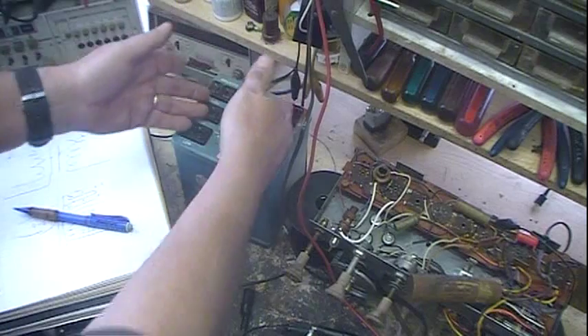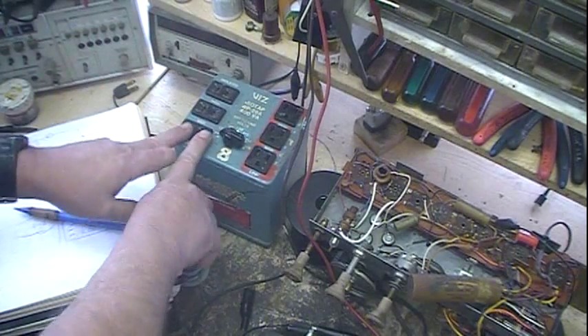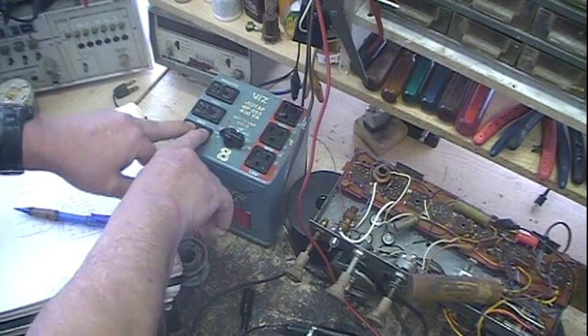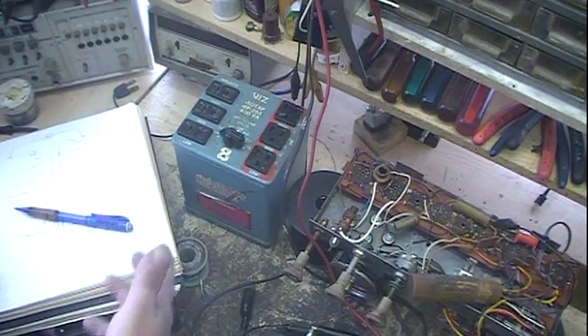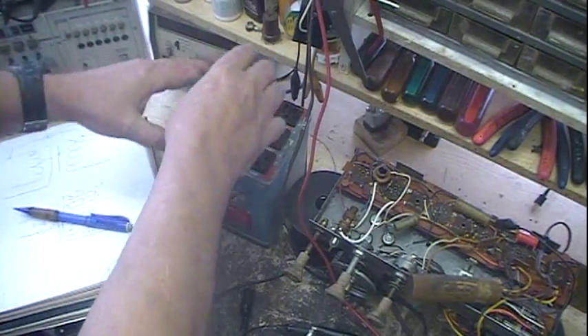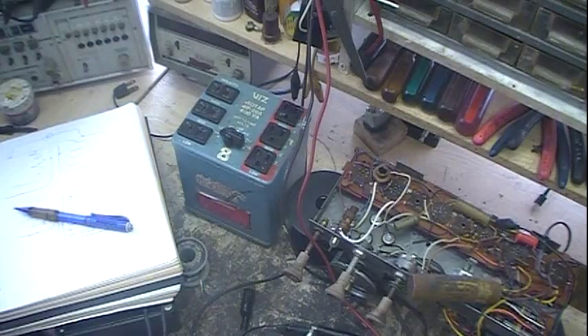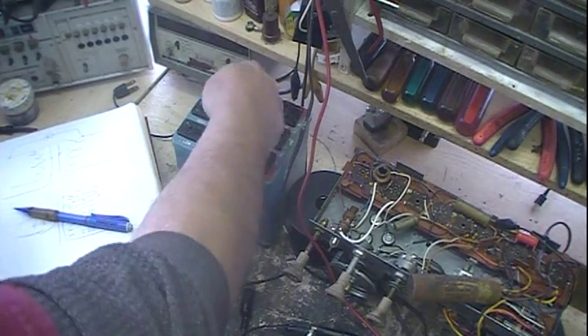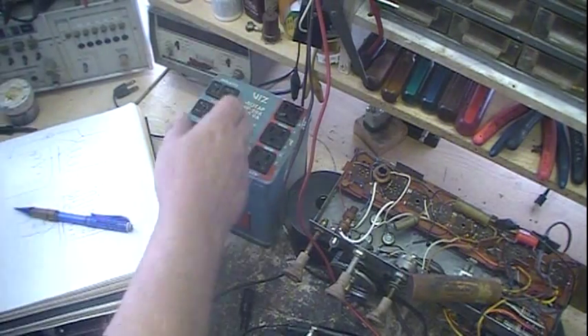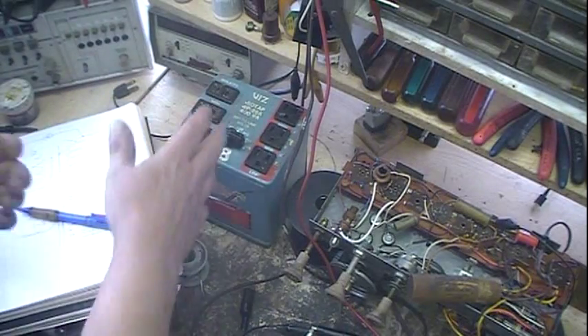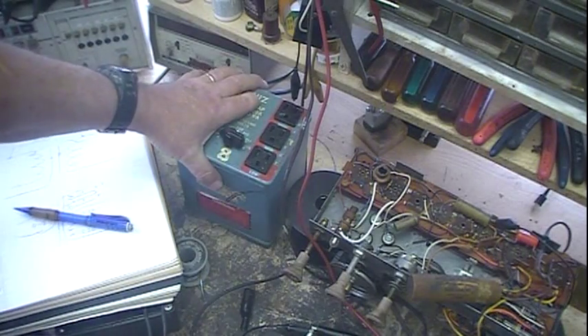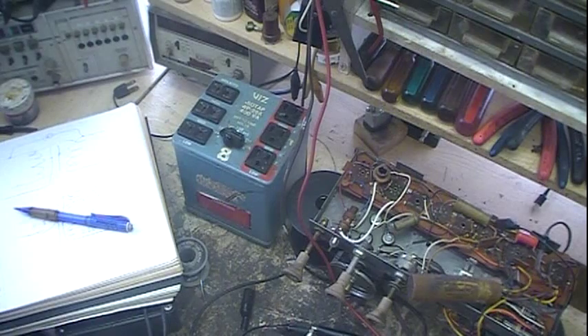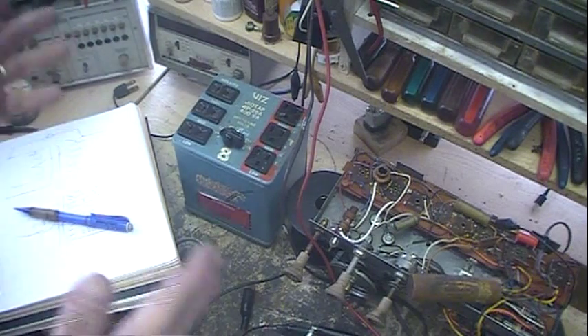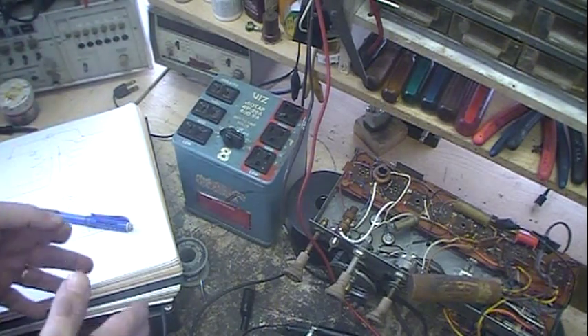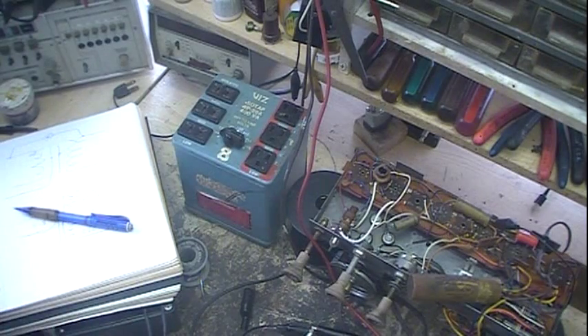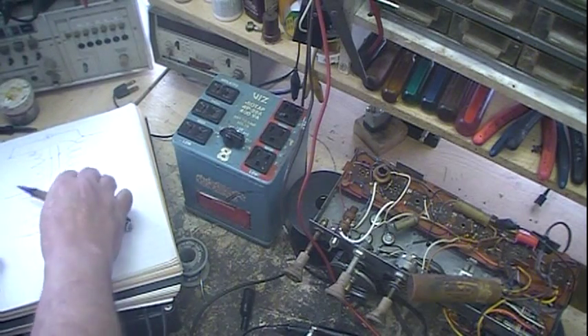Use the ohms range and check both sides, from this side to this side. If it's just a simple transformer where you've got just one plug and the cord, then just go from the cord to the plug, cord to plug, and then check ground. That's all you've got to do, and if it's reading open throughout, that transformer's fine, and you're good to go and perfectly safe.